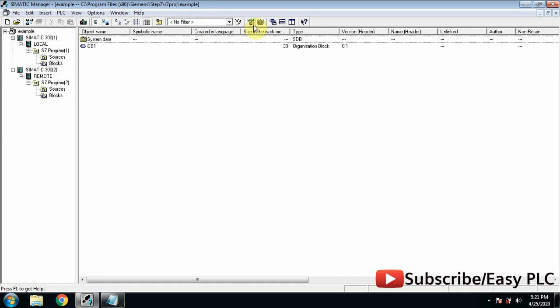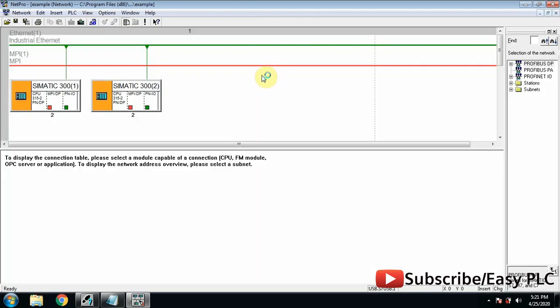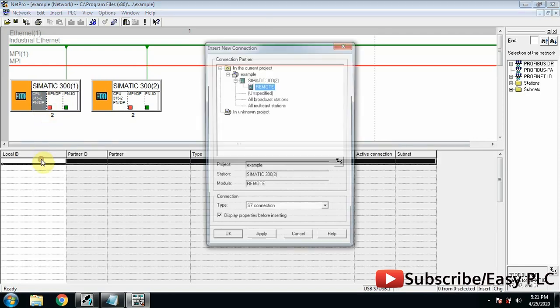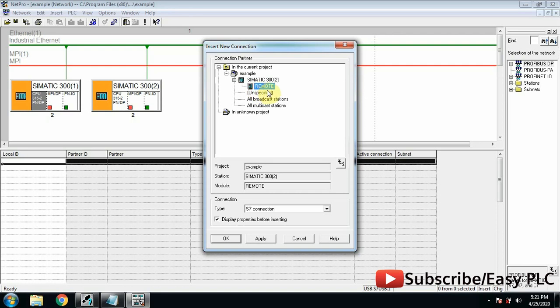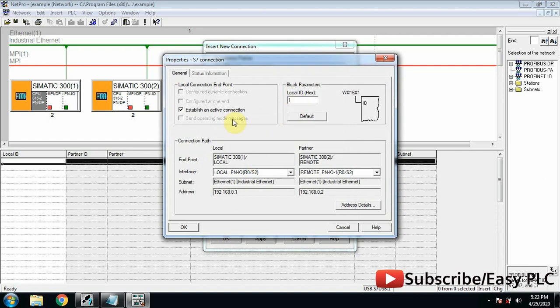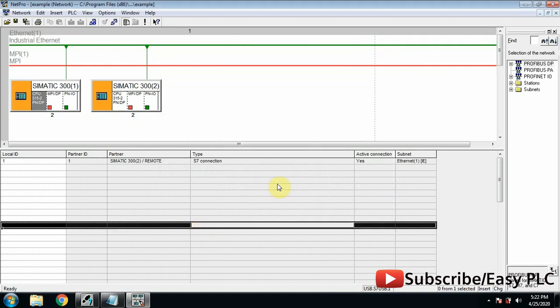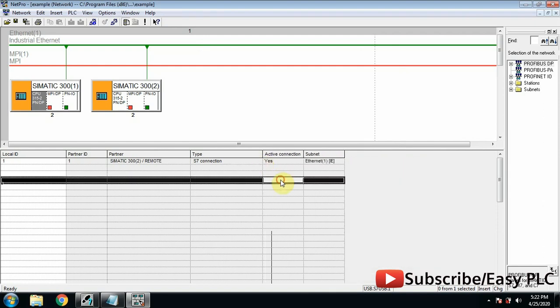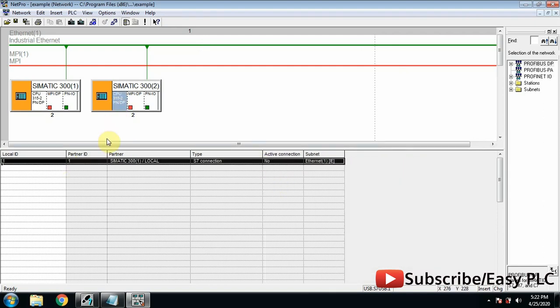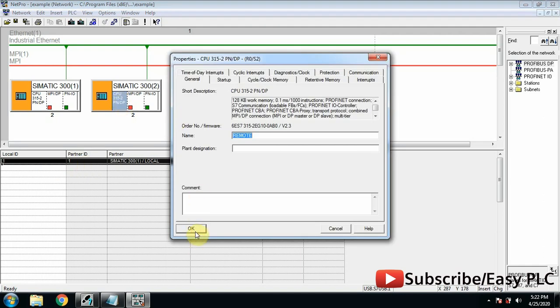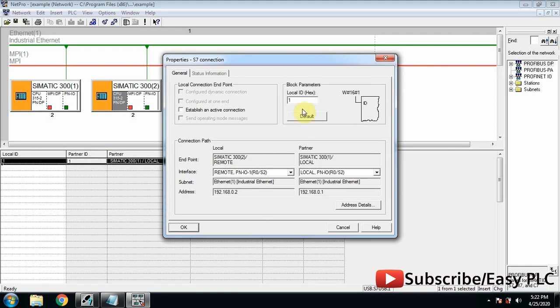Now we will go to the network configuration. As you can see it automatically selects the remote PLC. Click OK and verify the IP addresses for local and remote PLC. Now the setting is OK but there is a problem — both local ID and partner ID is one, which is wrong. To fix this, open the settings of the remote PLC and change its ID to 2.